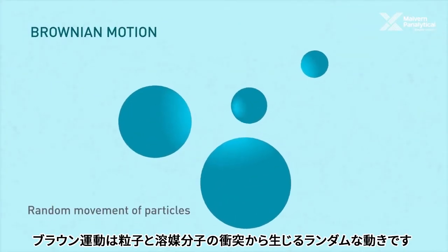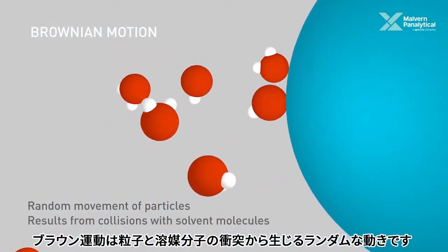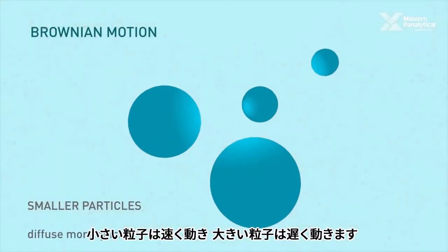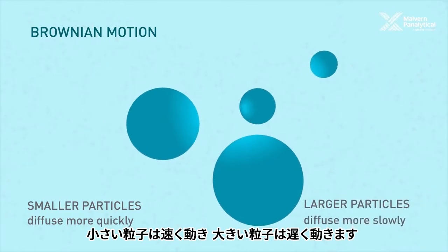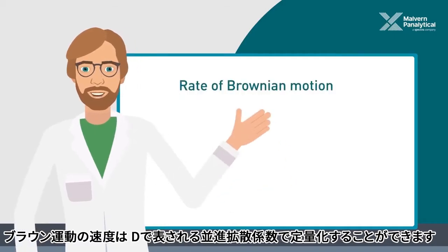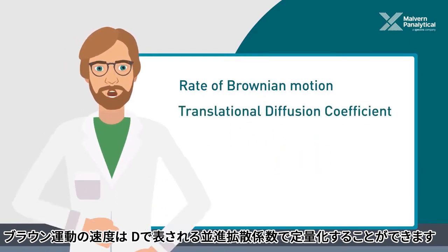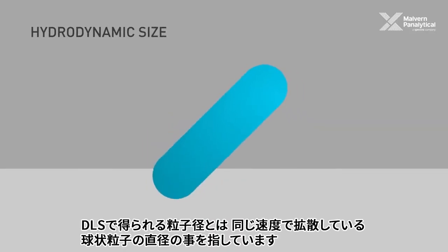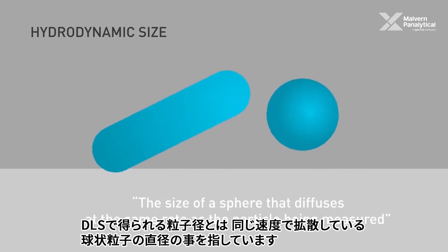Brownian motion is the random movement of particles which results from their collision with solvent molecules such as water. Smaller particles move or diffuse more quickly, and larger particles diffuse more slowly. The rate of Brownian motion is quantified as the translational diffusion coefficient, which is often represented by a capital D. The hydrodynamic size measured by DLS is defined as the size of a sphere that diffuses at the same rate as the particle being measured.